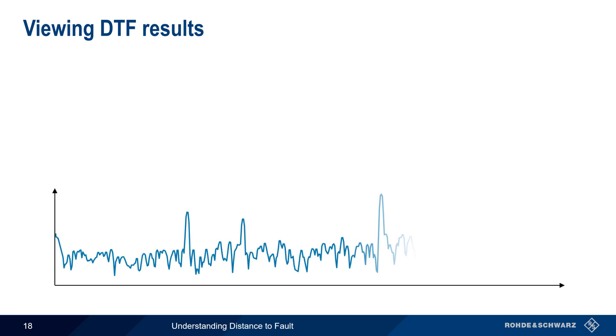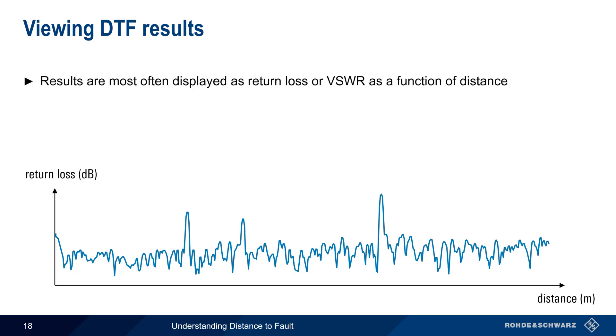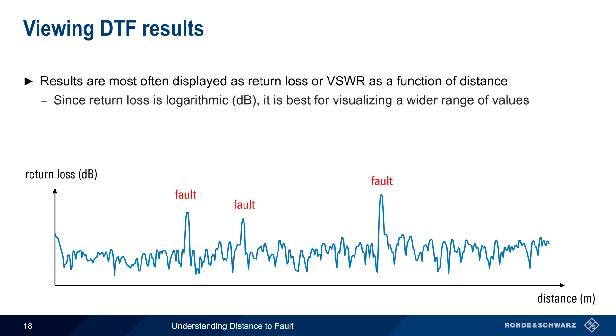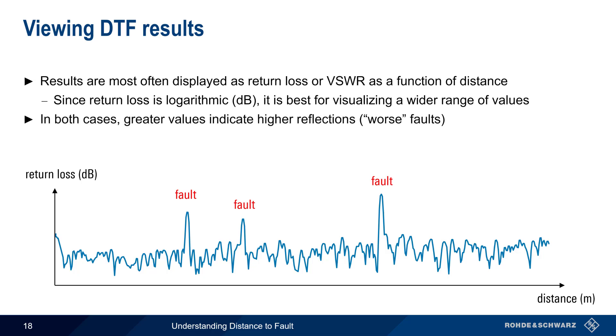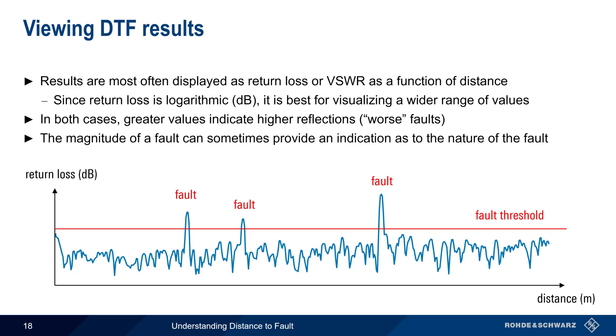After configuring settings and performing calibration, measurement results are normally automatically displayed when the cable under test is attached. Results are most often shown in the form of return loss or VSWR as a function of distance, and peaks in the plot correspond to faults. Since return loss is logarithmic and in units of dB, it is often a better choice than linear VSWR values when looking at a wide range of fault magnitudes. In both cases, greater values indicate higher reflections or worse faults. Many analyzers allow a threshold to be set for defining what constitutes a fault, and in some cases the magnitude of a fault can provide some indication as to the nature of the fault.